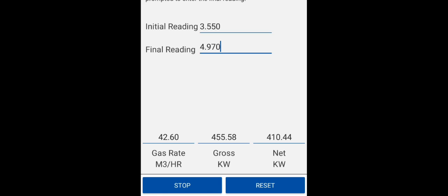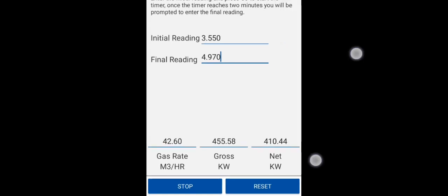A good thing with this is you can also use it to check if your gas meter is undersized. The meter at hand is a U100. We have two boilers, and if the other boiler when gas rated also requires 42.6 cubic metres per hour of gas, combined you've got about 85 cubic metres per hour. A U100 allows 100 cubic metres per hour to pass through, so the meter is the right size.